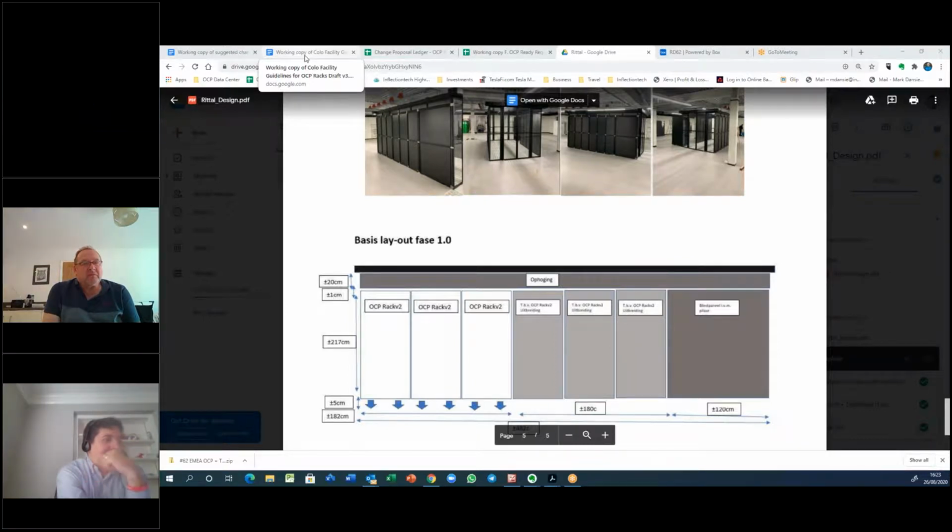This could be a place to provide a scale or guidelines around that, where the OCP user can have a conversation with their OCP cabinet designers, as well as their colo facility provider or data center provider or designers, and make sure that those meet up, because we are expecting at least 12 degrees delta T in terms of their set points, but obviously it can run up to 20 degrees and still be functional. And I know that there are quite a few pieces of kit out there these days that have that 20-degree delta T across their chassis. So coordinating delta T to airflow to power usage, we should be able to get some kind of chart, table, or guideline to inform and educate an end user.